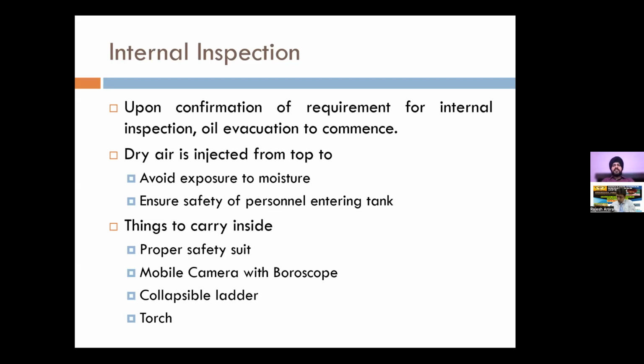And besides ensuring the safety of our personnel, we also need to ensure the safety of our transformer, because we are going to inspect it. So a proper safety suit needs to be worn by the people who enter. This will ensure that external dust, dirt, or other such things do not enter the transformer. So this safety suit will also ensure that our personnel are safe, and our equipment is also safe. There is sort of a bubble formation between the two, even when they are inside.